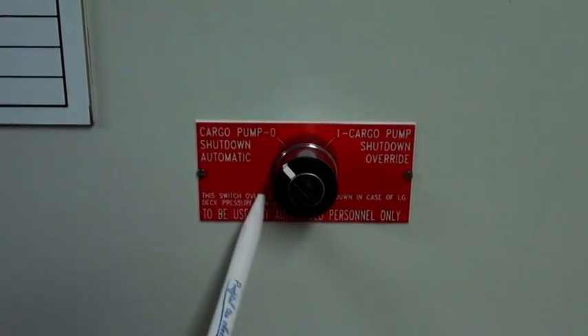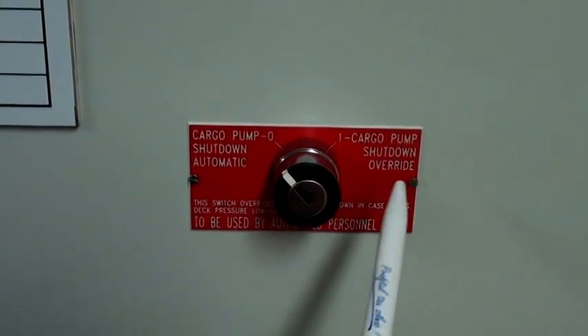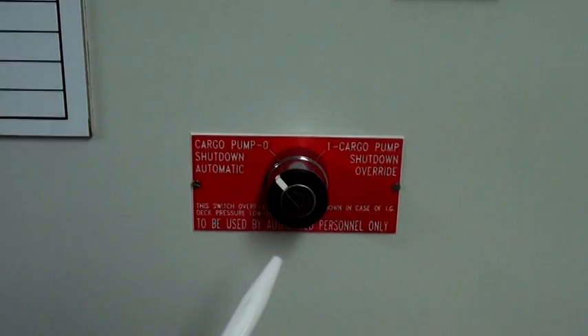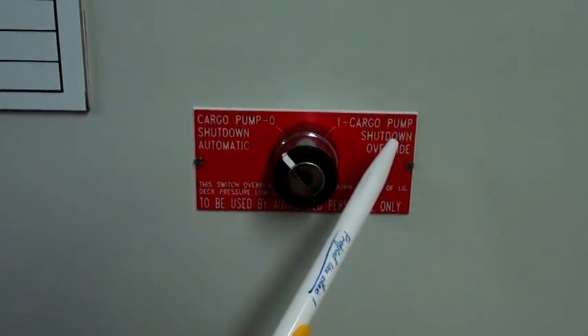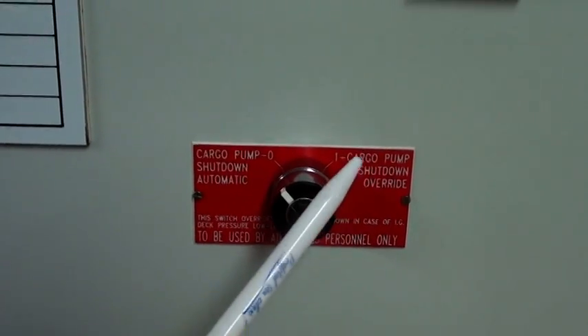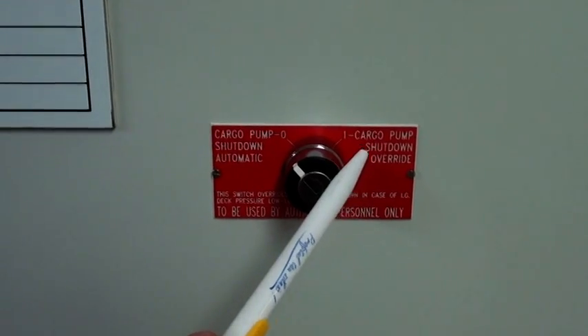In case the IG has low-low pressure on deck, you can switch over to cargo pump shutdown overriding and the system will not shut down the cargo pumps. But this should be made only according to the company policies.